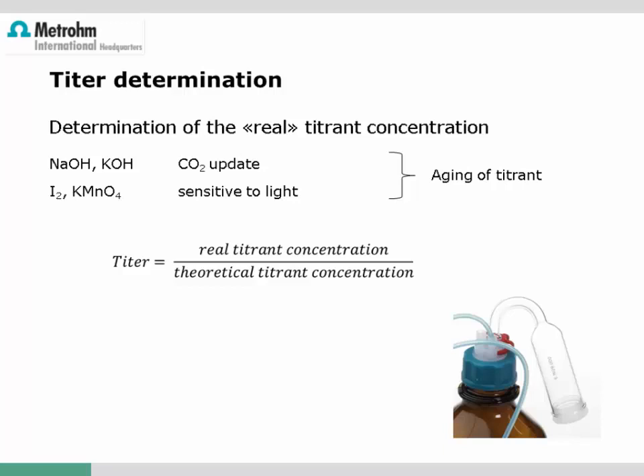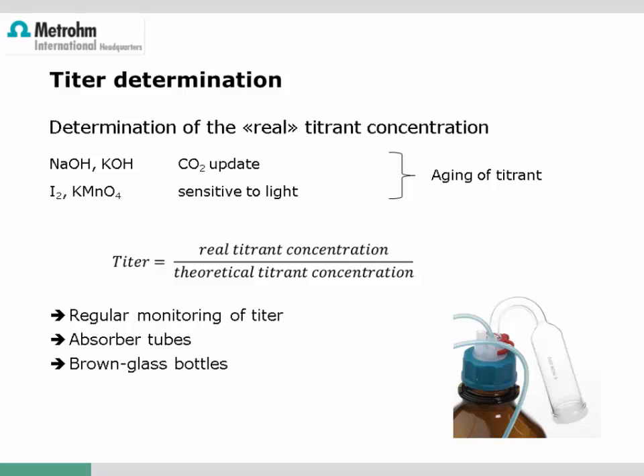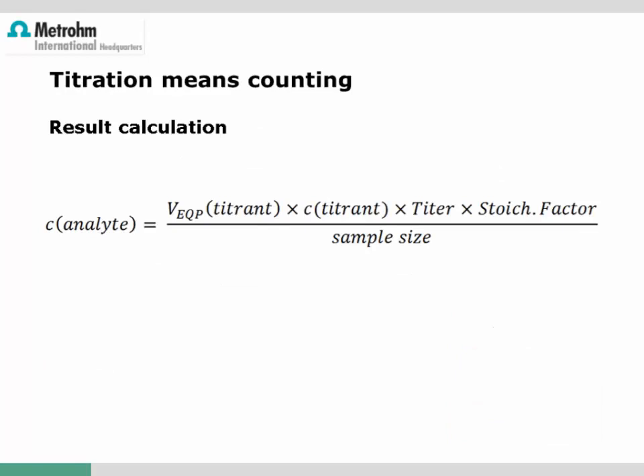The titer factor is calculated from the real determined concentration divided by the nominal concentration. We recommend monitoring the titer frequently, depending on the stability of the titrant. The aging of the titrant can be reduced by using countermeasures like absorber tubes, brown glass bottles for light-sensitive solutions, or storage at cool temperatures.